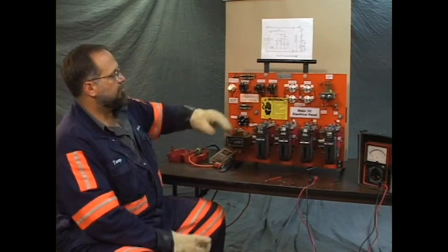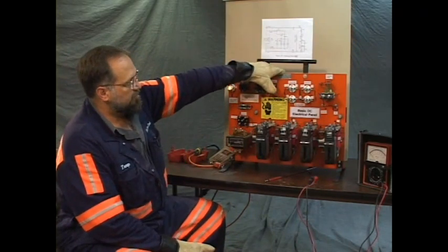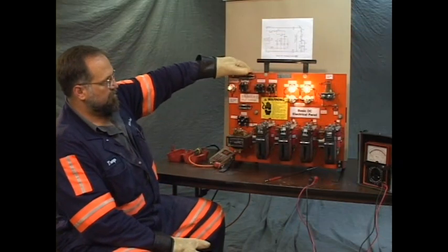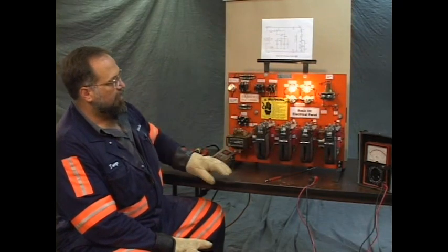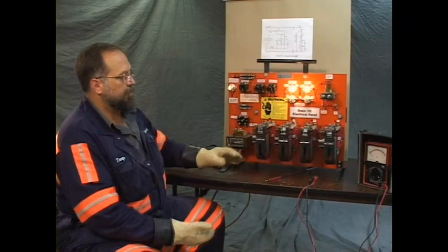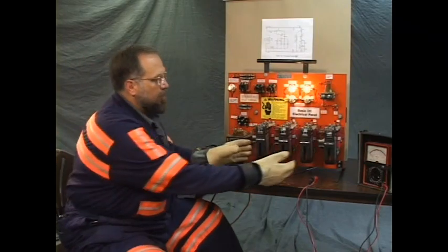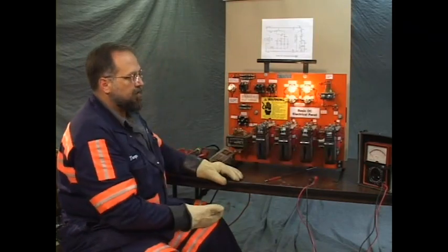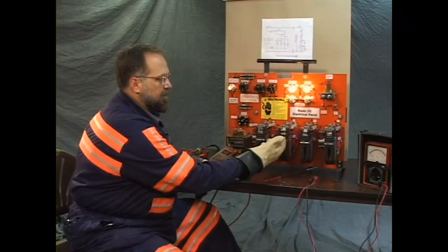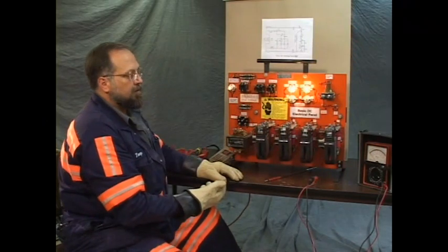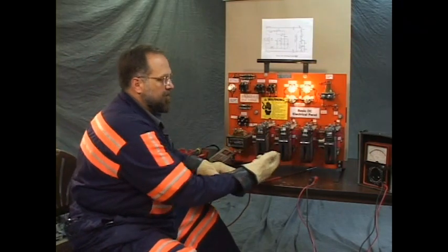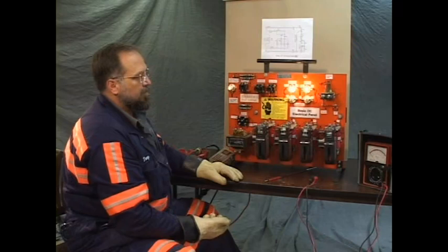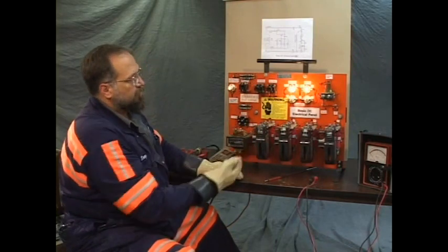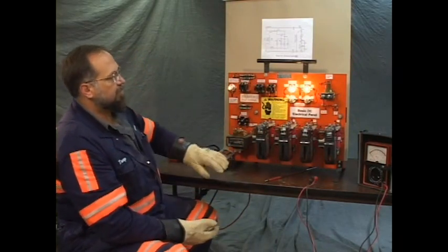Here we go. Watch the lights. You'll note when we start, you hear 3 clicks. M1 and M2 close simultaneously. Then after a 1 second interval, 1A closes. After a 1 second interval, 2A closes. With those closures, the lights change.